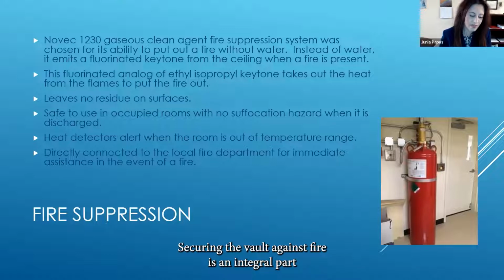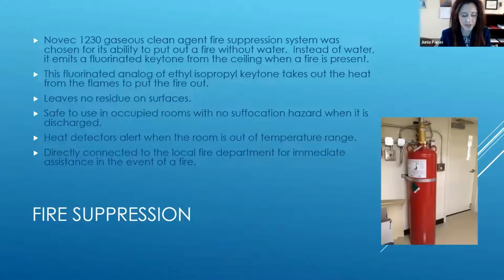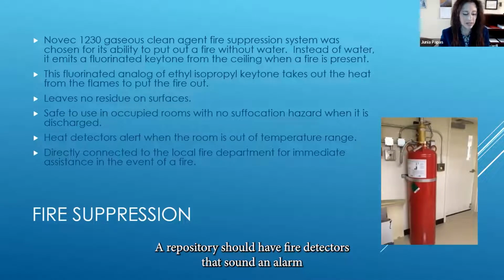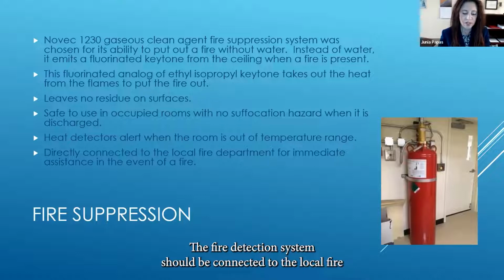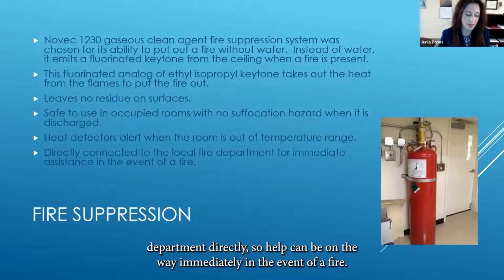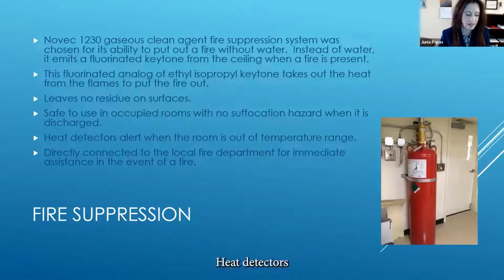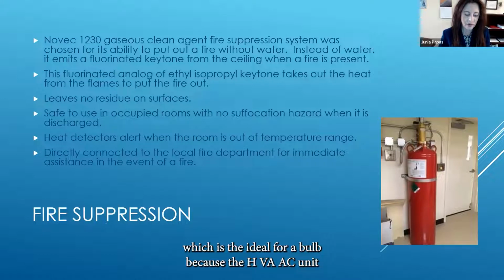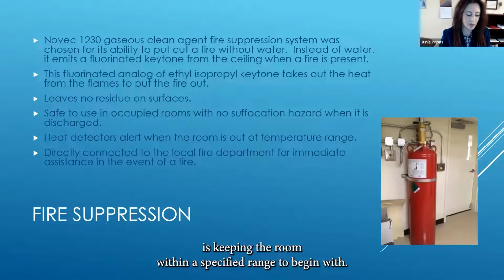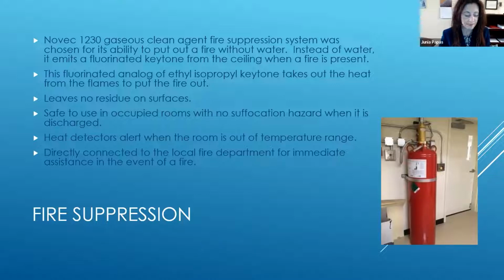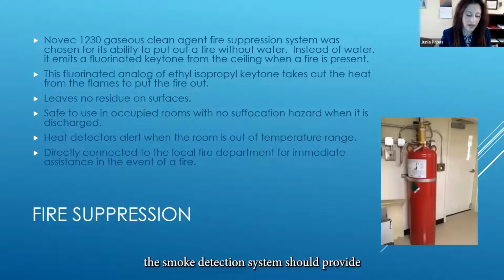Securing the vault against fire is an integral part of the long-term preservation of archival materials. A repository should have fire detectors that sound an alarm when a fire is present. The fire detection system should be connected directly to the local fire department, so help can be on the way immediately in the event of a fire. Heat detectors operate on the basis of a fixed temperature range, which is ideal for a vault because the HVAC unit is keeping the room within a specified range to begin with. According to NARA Directive 1571, the smoke detection system should provide 99% reliability of detecting the origin of a fire in less than 5 minutes.